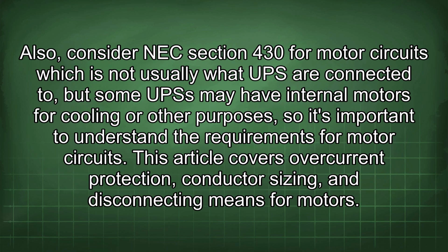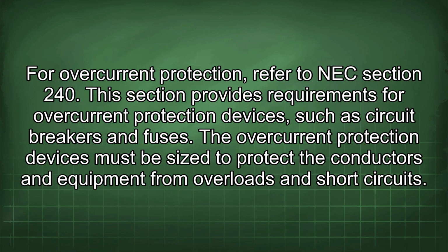Also, consider NEC Section 430 for motor circuits, which is not usually what UPS are connected to, but some UPS may have internal motors for cooling or other purposes, so it's important to understand the requirements for motor circuits. This article covers overcurrent protection, conductor sizing, and disconnecting means for motors. For overcurrent protection, refer to NEC Section 240. This section provides requirements for overcurrent protection devices, such as circuit breakers and fuses. The overcurrent protection devices must be sized to protect the conductors and equipment from overloads and short circuits.